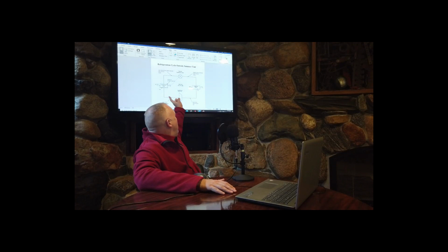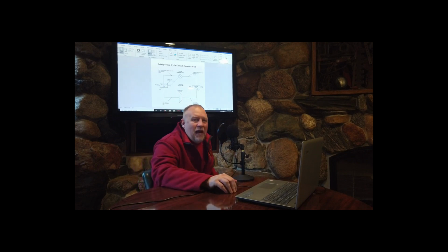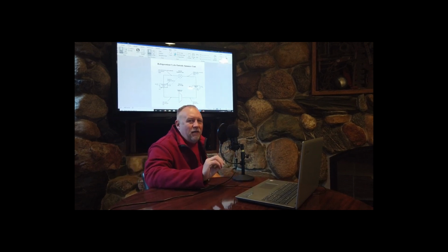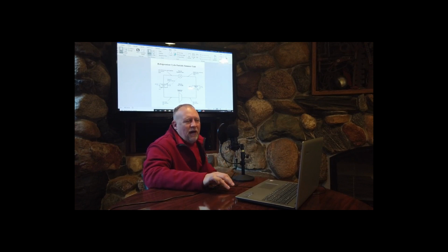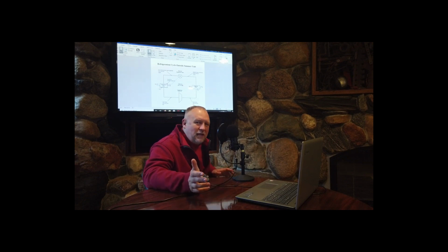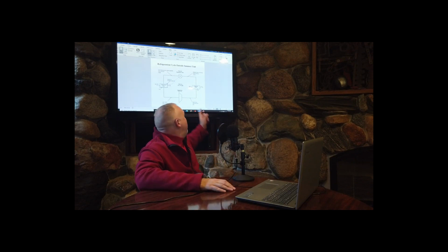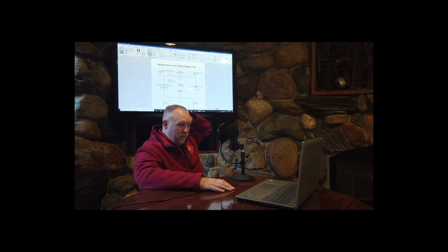The ideal gas law that caused this vapor to get hot when we compress it works in reverse here. Ideal gas law strikes again. As that evaporator allows that vapor to expand, the coil gets cold. We hit it with return air. That return air is relatively warm, and we cool it down to supply air temperature. Now it's 55 degrees, or at least right about where we want it to be. It gets turned into supply air, and we use a fan to blow that supply air into the room for air conditioning.